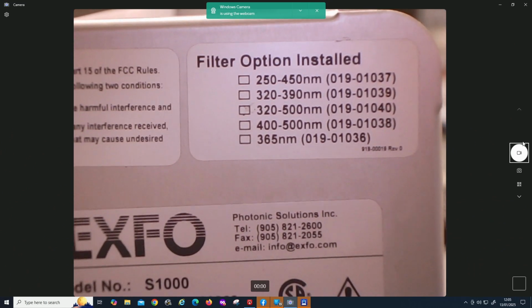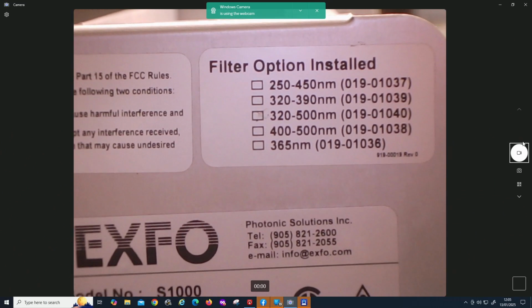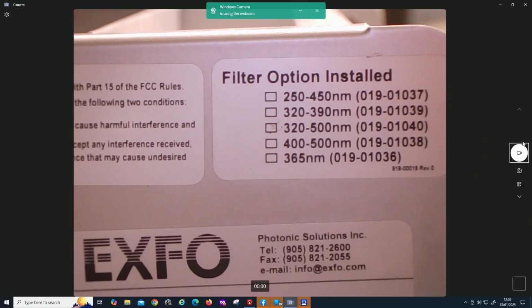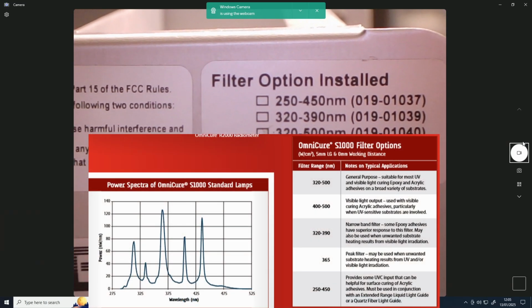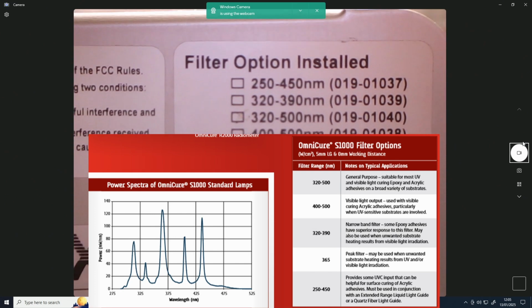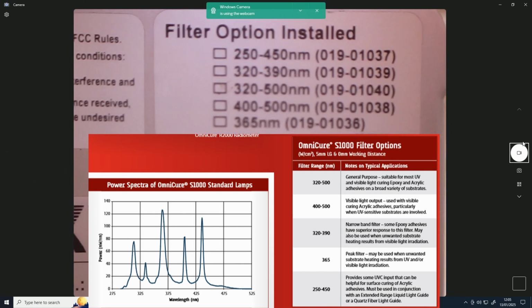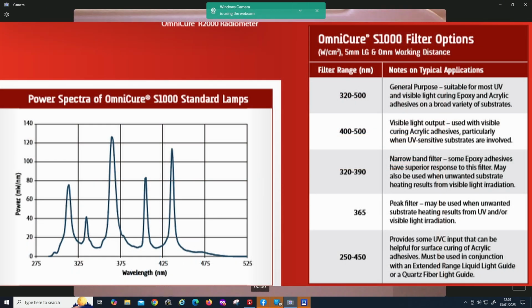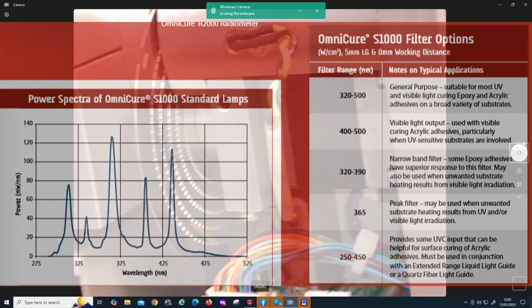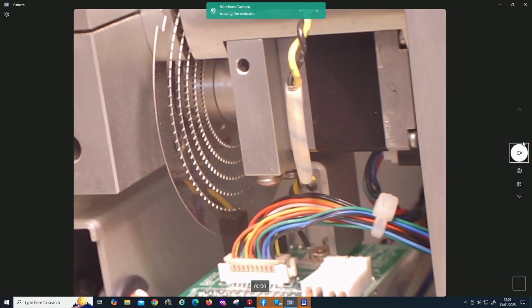Now buried in here somewhere, there's also a filter. If I look at the back panel, you can just see that it's got a 320 to 500 nanometer filter option fitted, and that's sort of a general purpose filter. And you can see there's loads of other filters you can fit on there, but this has got the general purpose one fitted, which is just great, really. If you go to 250, then that's a bit more dangerous for the skin and the eyes and everything. So unless you really need 250, you don't want to be down there. One of the reasons that they do these different things, by the way, and some of them are narrower, is so that if you're working on a very sensitive component, you're limiting the amount of energy that's getting spilled out from that and heating nearby objects.